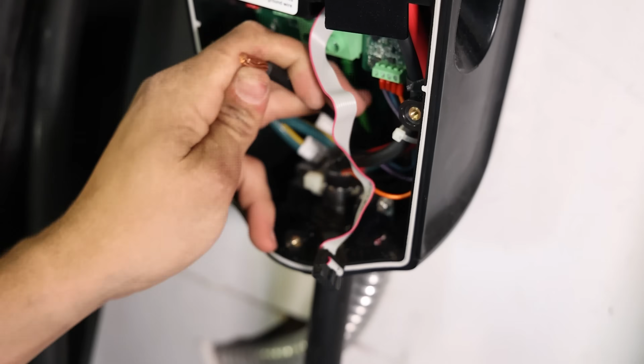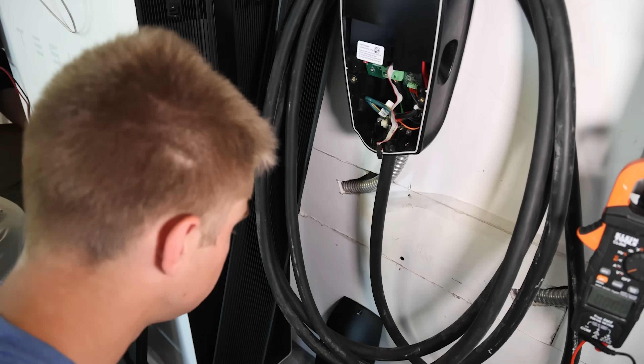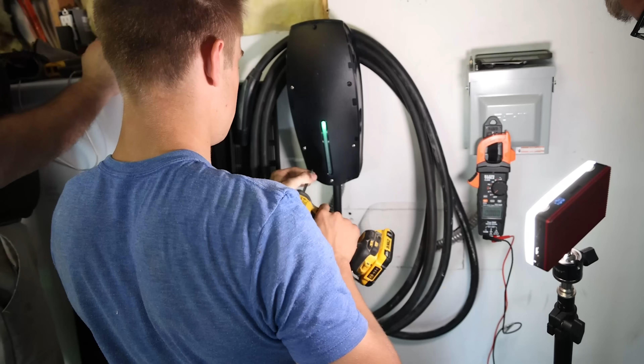Tesla wall connector, which we did not install. When we relocated the circuit breaker and pulled on the metal flex, the conductors literally slipped out of the terminals and were hanging energized inside of that. It wouldn't have harmed anyone, but if they had arced, it would have created quite the pop. So, little bits and pieces here to pull together. Camden found it, he's making the fix. Good work, Cam.